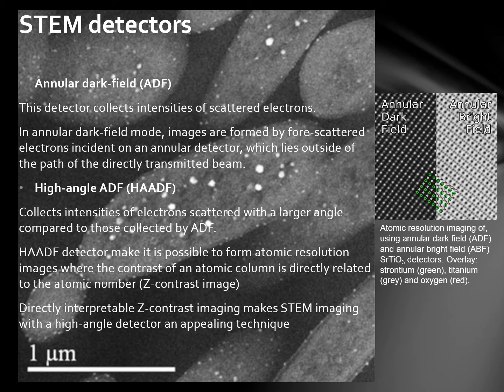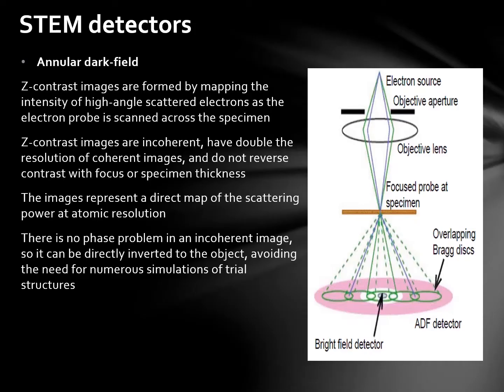Directly interpretable Z-contrast imaging makes STEM imaging with a high angle detector an appealing technique. Z-contrast images are formed by mapping the intensity of high angle scattered electrons as the electron probe is scanned across the specimen. Z-contrast images are incoherent, have double the resolution of coherent images, and do not reverse contrast with focus or specimen thickness. The images represent a direct map of the scattering power at atomic resolution. There is no phase problem in an incoherent image, so it can be directly inverted to the object, avoiding the need for numerous simulations of trial structures.